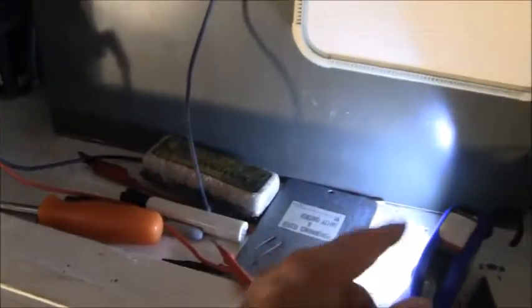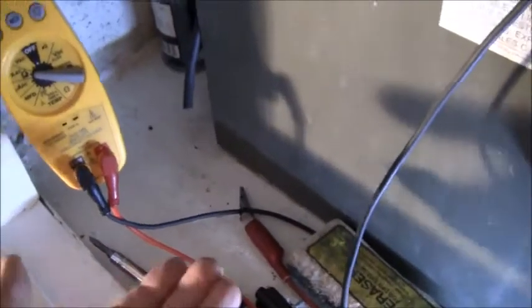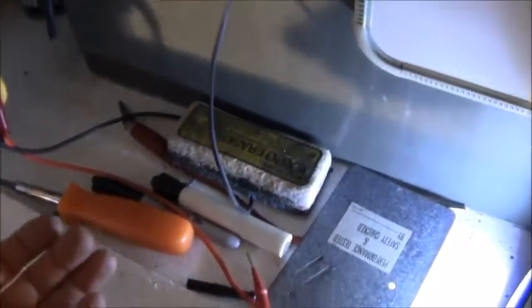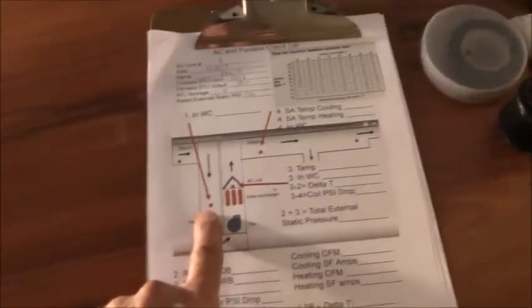I know that my filter is in the back of the door right here. Shut this light off, put it at an angle. So I know that my filter is right under the door here because the air comes in and comes up. So what I did is I drilled a hole right there, and it's on the other side of this plywood that this unit sits on. That is going to be the same thing as a pre-filter reading because it's on the opposite side.